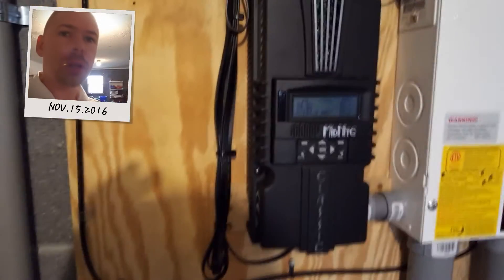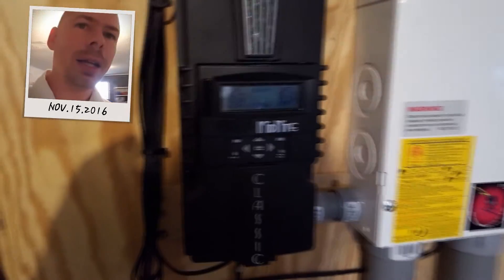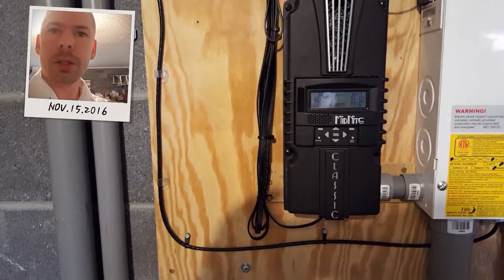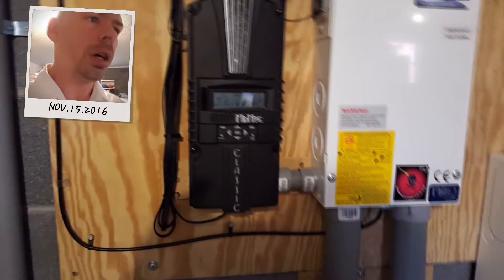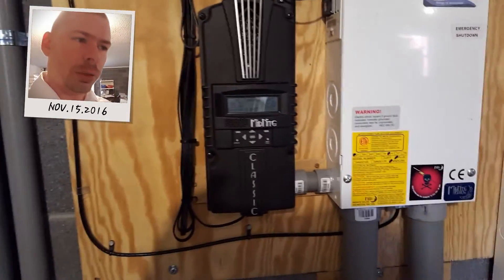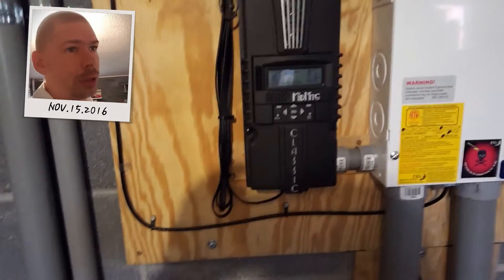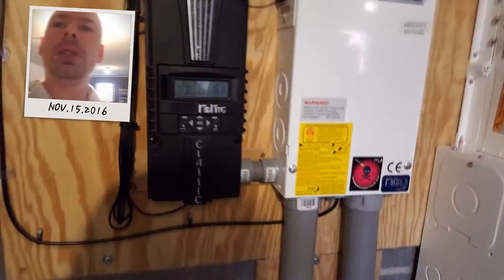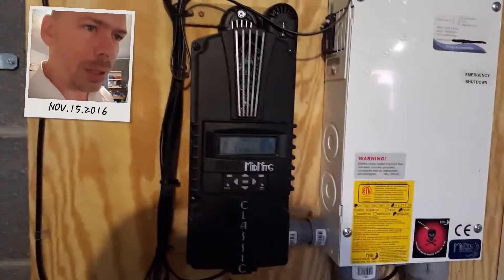This is your charge controller — it's a MidNite Classic. I do not recommend going over the rated wattage. For instance, if you have a 24-volt system and you want to put 3,000 watts on it, you need to get two charge controllers because you're going to kill it. But let's not talk about that — this is just a basic overview of my system.